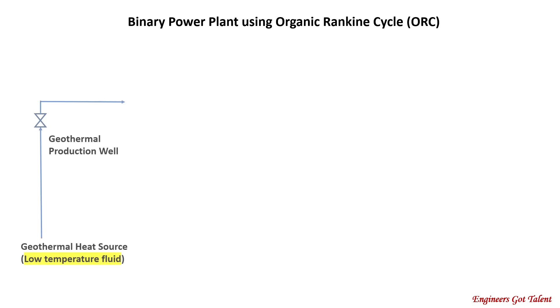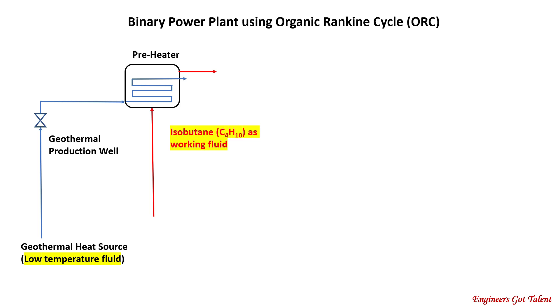These are the major components of a Binary Power Plant using the ORC system. First is the geothermal production well, where it serves as a conduit of hot fluids from the geothermal source of 110 degrees Celsius to the preheater. Next is the preheater, which initially boils the incoming liquid isobutane to a partially gaseous vapor using heat coming from the geothermal hot fluids. Next is the evaporator, where further boiling and heating is applied to the partially gaseous isobutane vapor using the 80 degrees Celsius heat from the geothermal fluid. Note that the isobutane will start to boil at only minus 11.7 degrees Celsius.